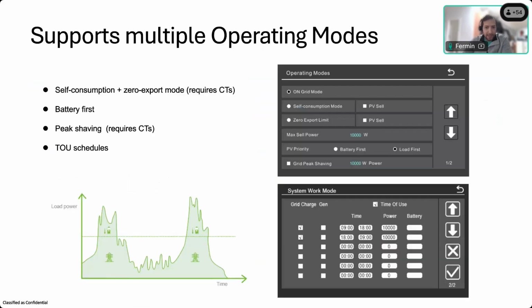And the last but not least is the multiple operating modes. This allows you to operate the system in different modes. The self-consumption mode allows you to use the most power from the system, either PV or battery, to power your home loads. And you can also set the system to zero export mode. So let's say the batteries are fully charged and there's surplus PV power, you can set up the system to ramp down the PV power so it doesn't export any power to the grid. You can also set the system to battery first, meaning that it can charge the battery at full rate from PV or grid, or both at the same time.